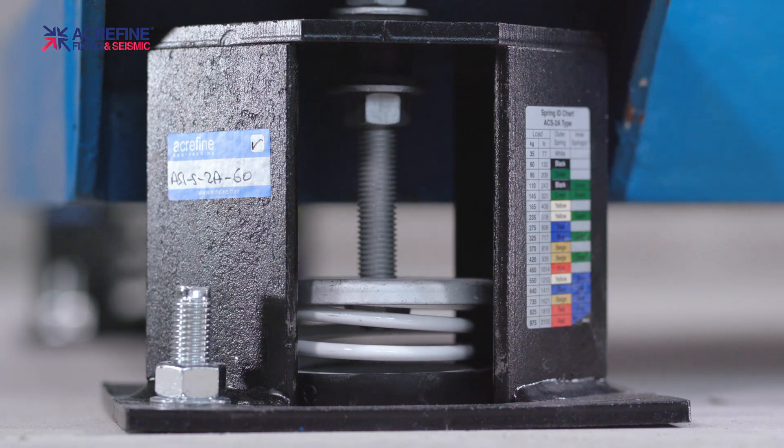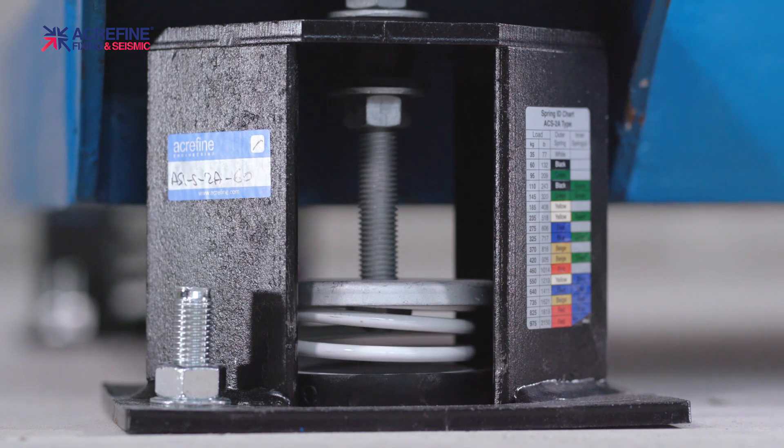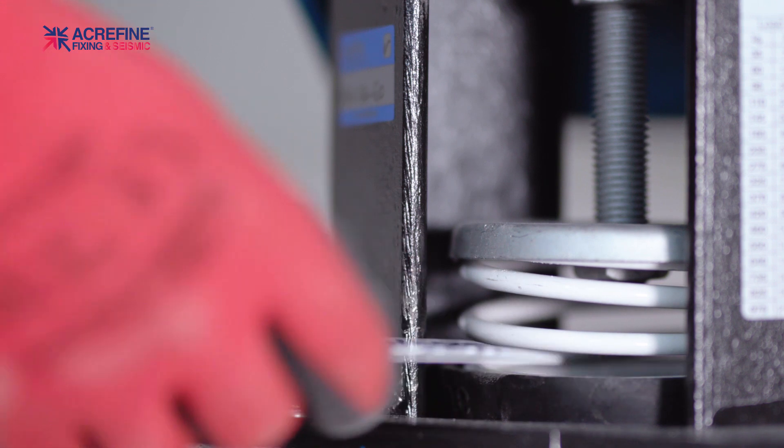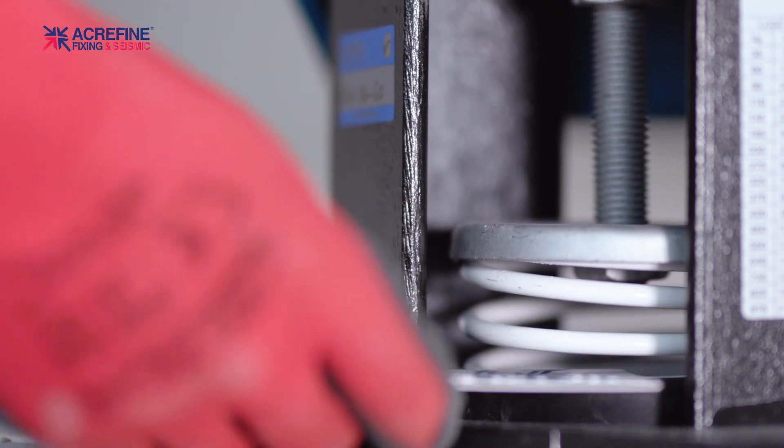For maximum vibration isolation performance, the more compression the better unless the springs are locked. To check, put something as thin as a plastic card inside the spring and see if it fits.